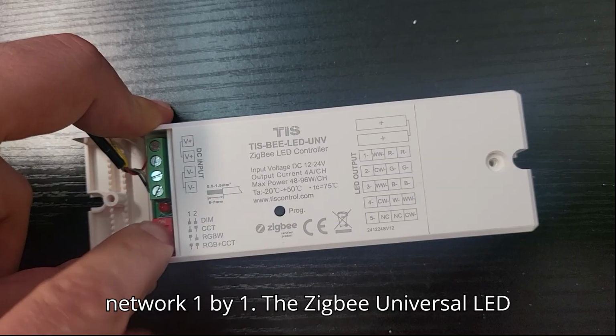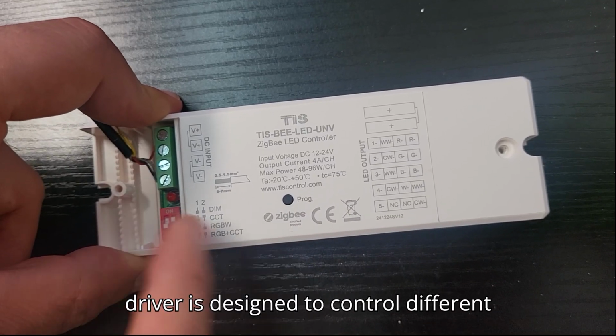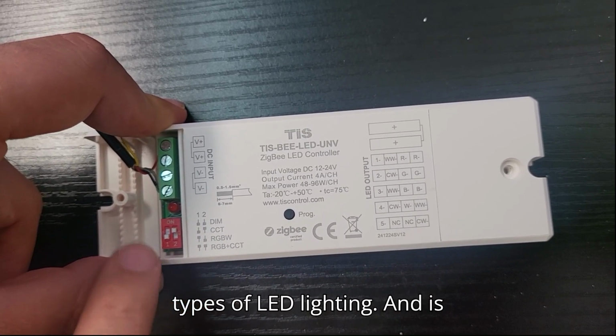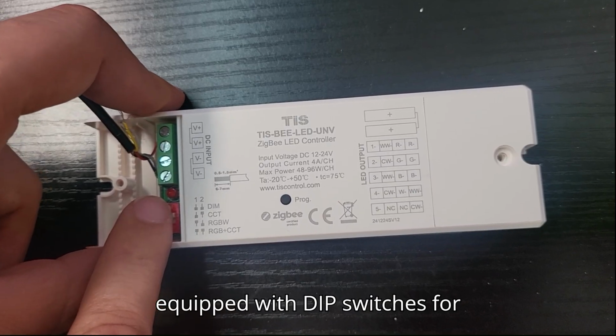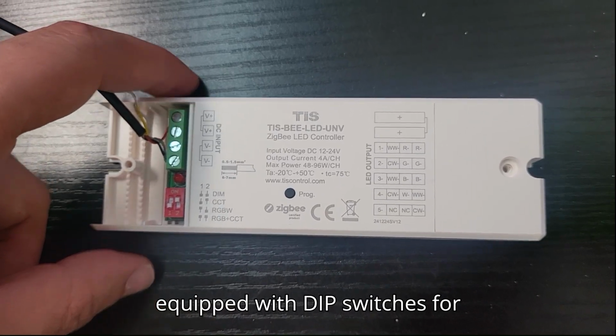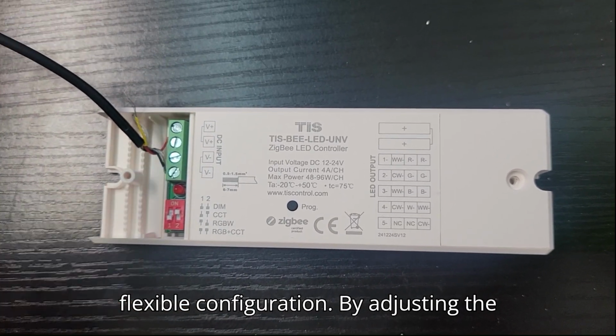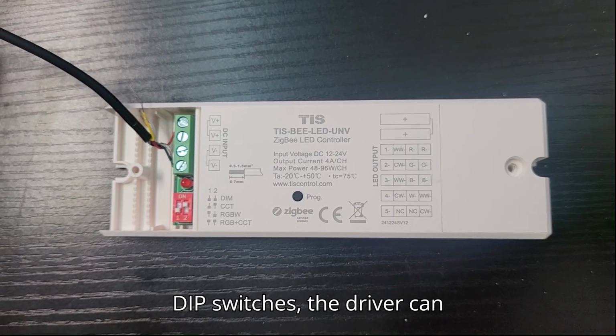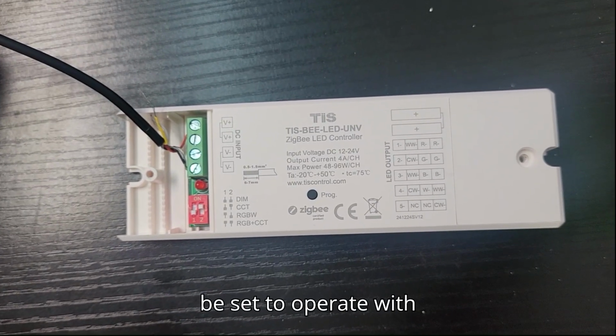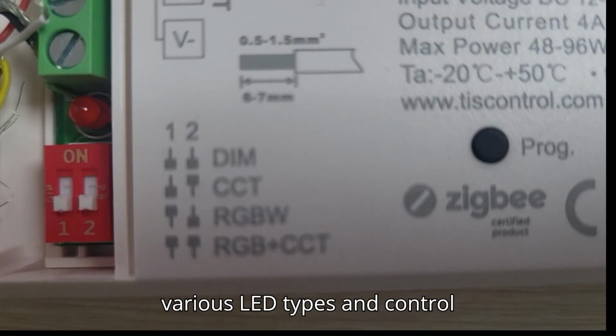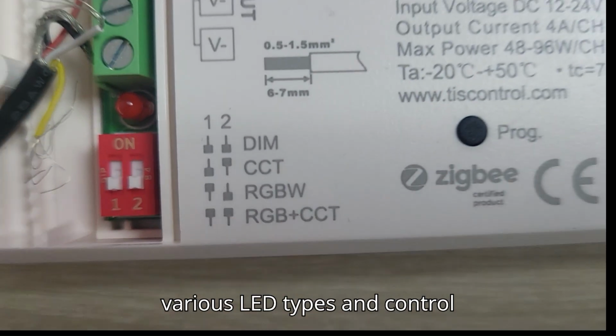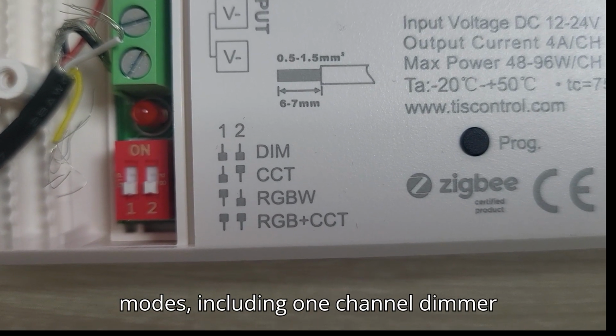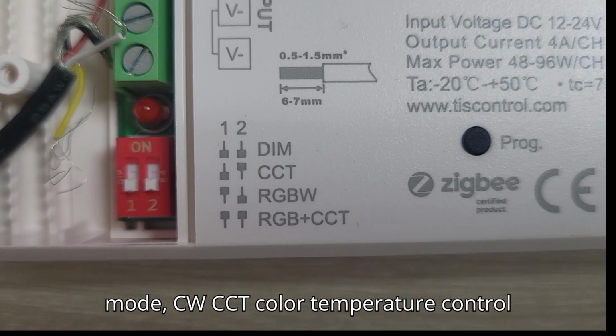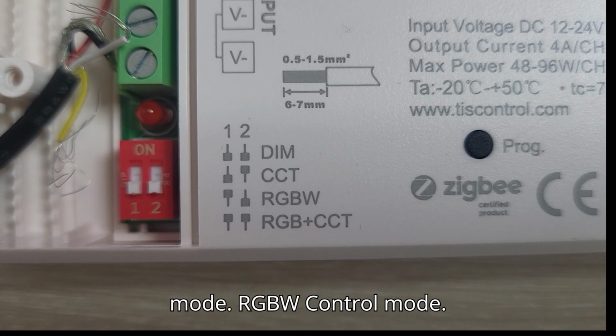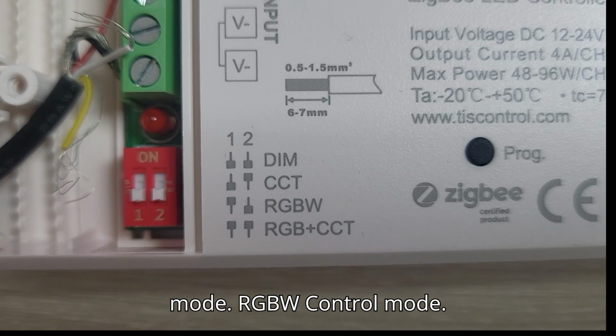The ZigBee Universal LED driver is designed to control different types of LED lighting and is equipped with dip switches for flexible configuration. By adjusting the dip switches, the driver can be set to operate with various LED types and control modes, including 1-channel dimmer mode, CW, WW color temperature control mode, and RGBW control mode.